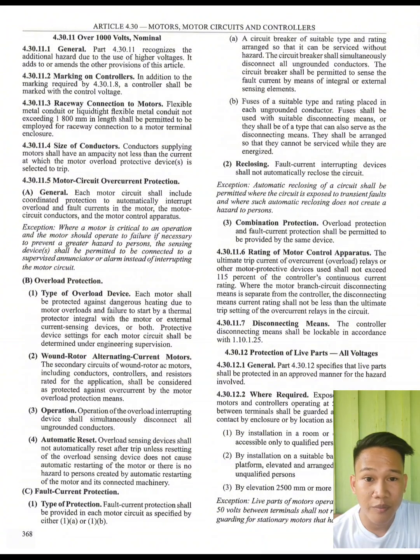Next is B, overload protection. So there are types of overload protection. First, type of overload device. Each motor shall be protected against dangerous heating due to motor overloads and failure to start by a thermal protector integral with the motor or external current sensing device or both. Protective device setting for each motor circuit shall be determined under engineering supervision.